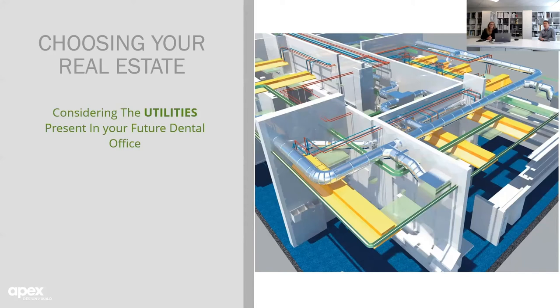With all these different systems, it is all the more important to look at the factors such as the size of the space and these existing systems to ensure that we achieve the necessary flow rate. We want to see a minimum of 12 air changes per hour. Taking measures to improve ventilation in these areas or the rooms where someone was ill or suspected to be ill with COVID-19 will help shorten the time it takes respiratory droplets to be removed from the air. We mentioned earlier that we recommend creating negative air pressure and exhausting the air or running it through HEPA filters.